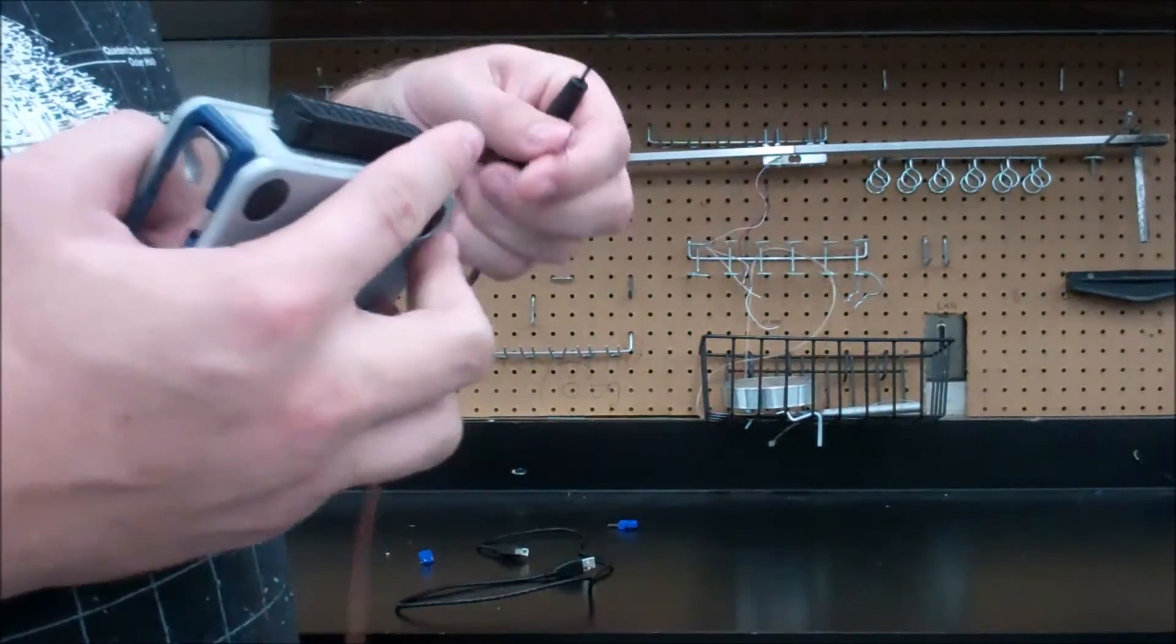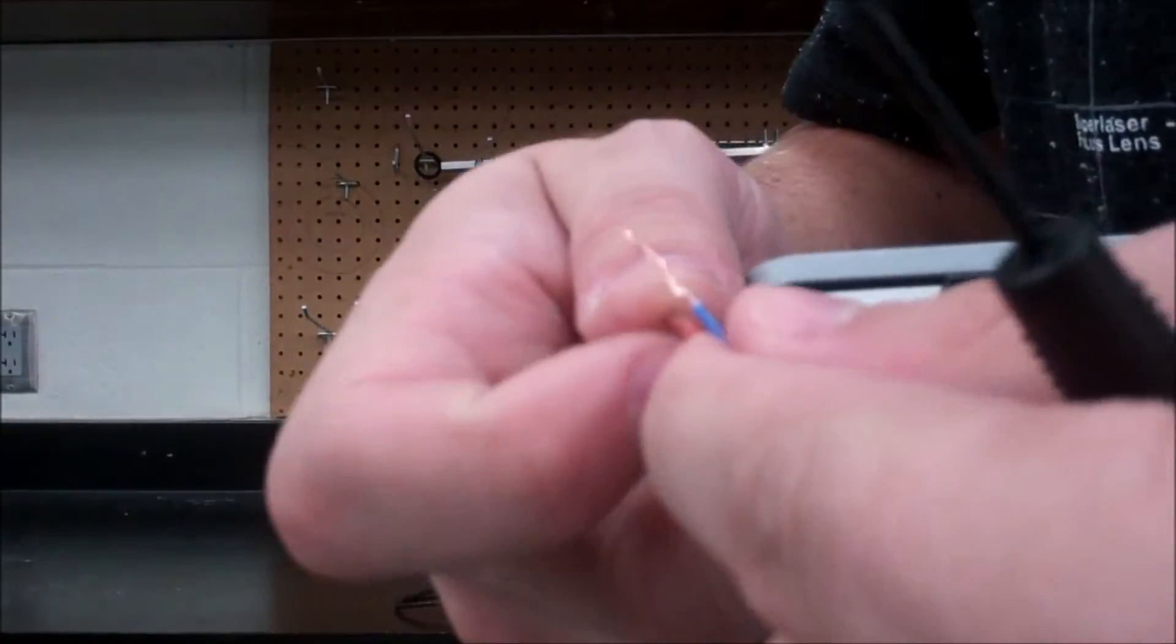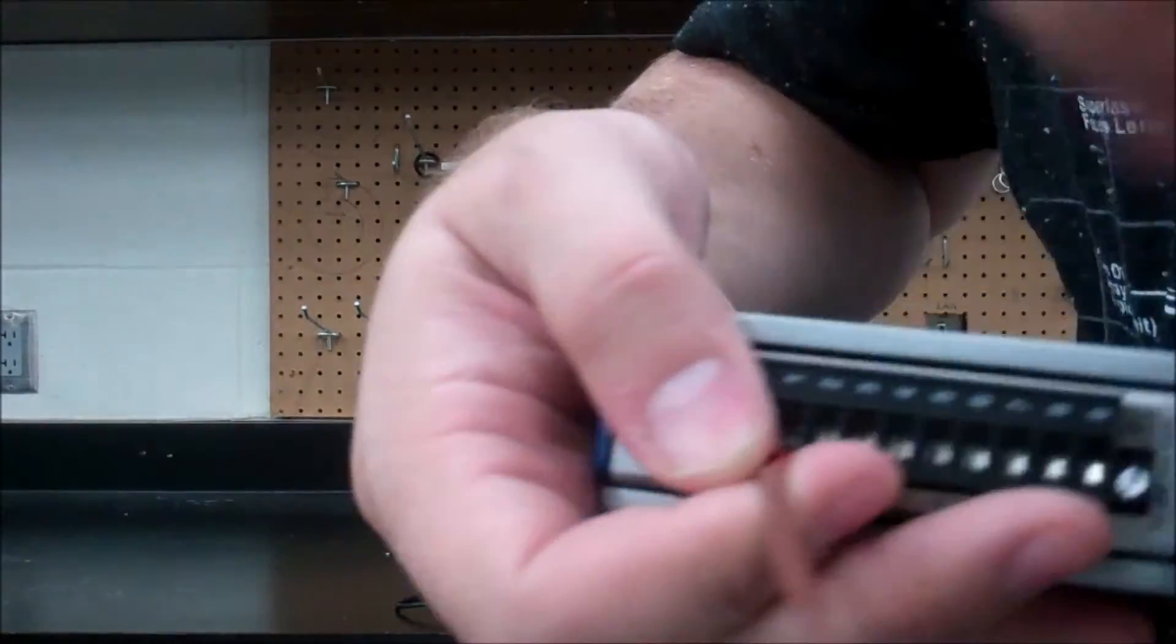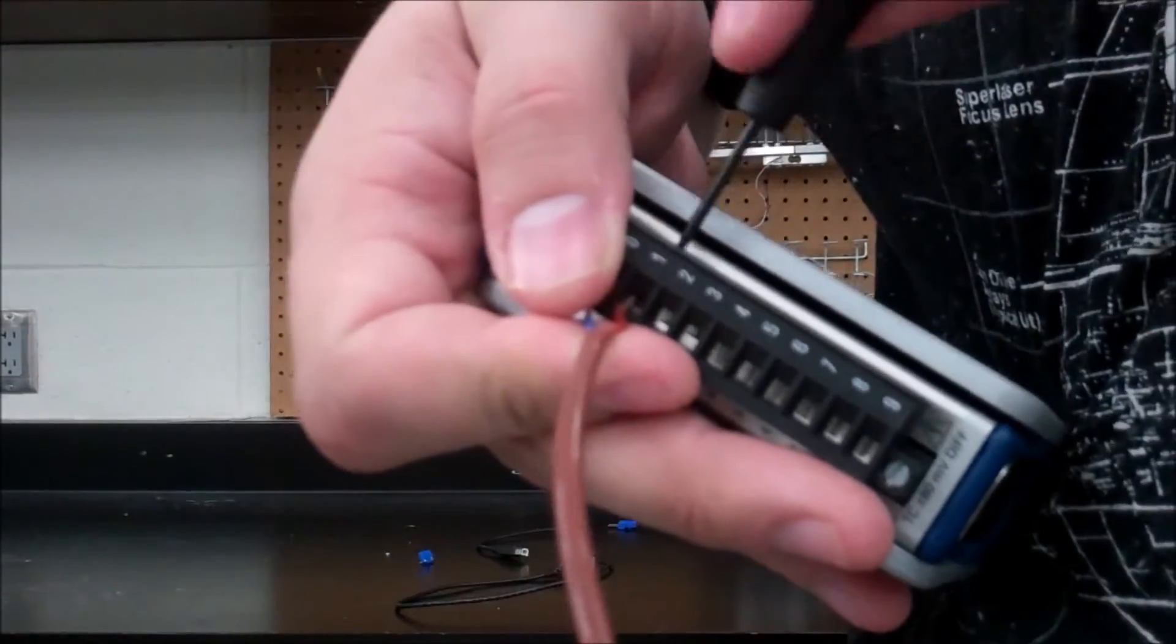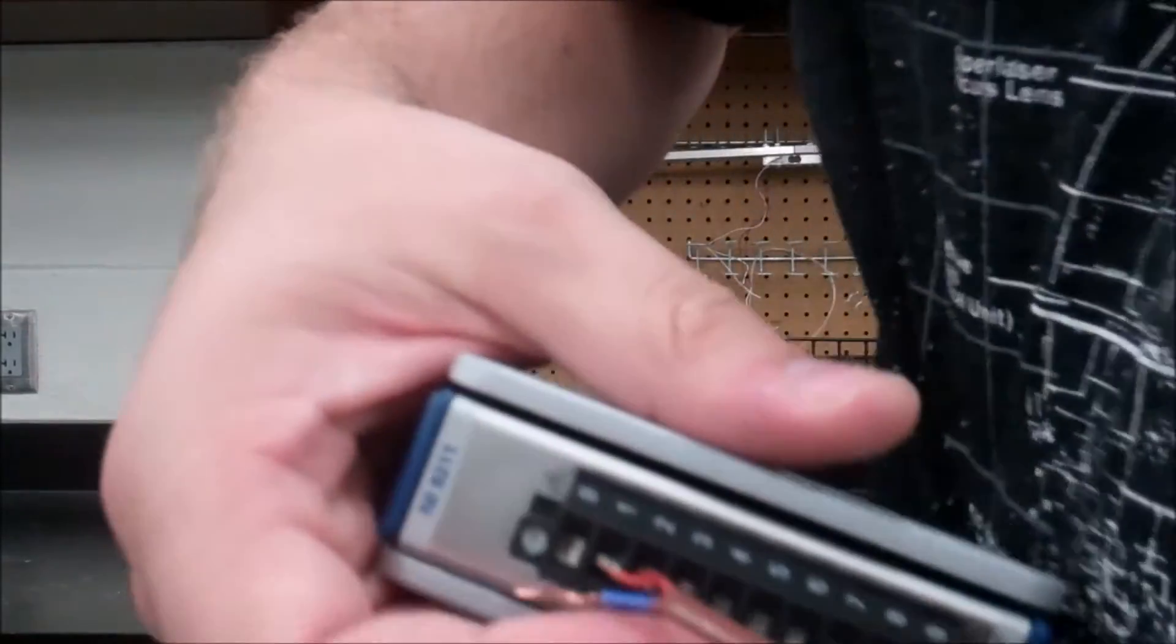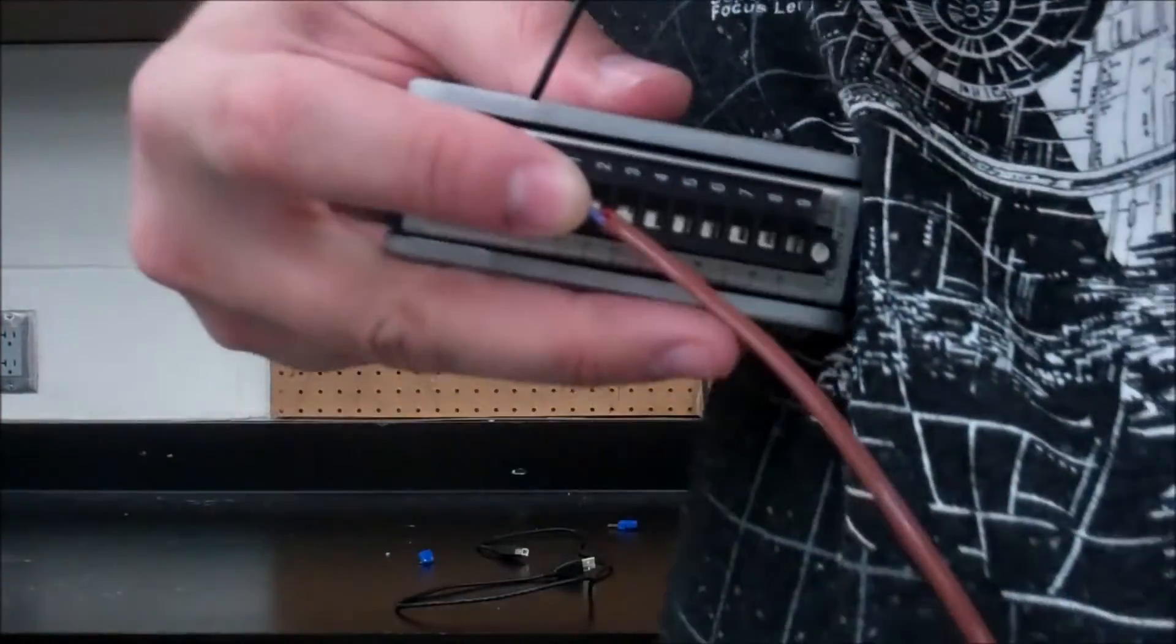If not, flip the polarity and then go from there. So for thermocouple one, which is the first thermocouple, you can hook up up to four. You go ahead and put the silvery cable in the one port and tighten the screw up. And then in the zero port you put the copper colored wire and then go ahead and screw it up.